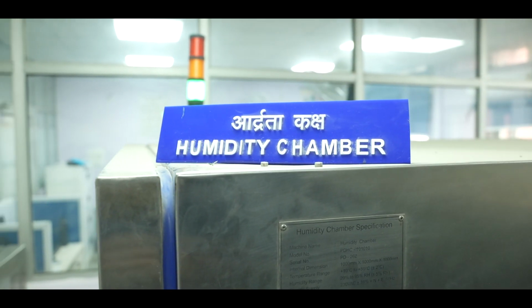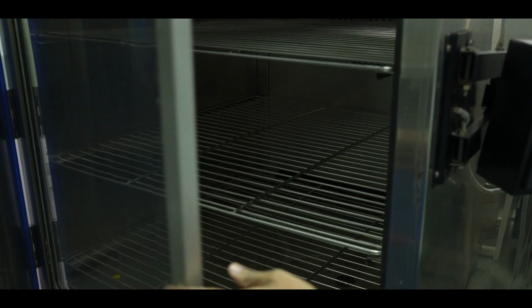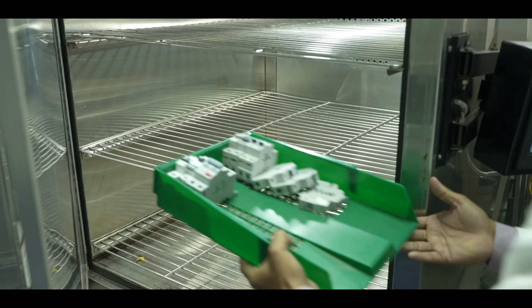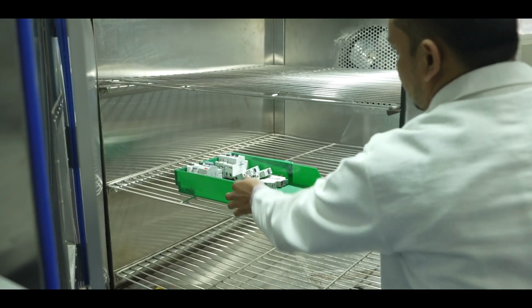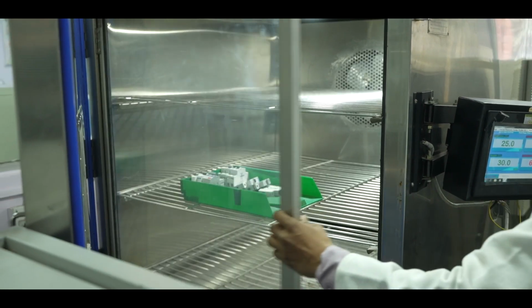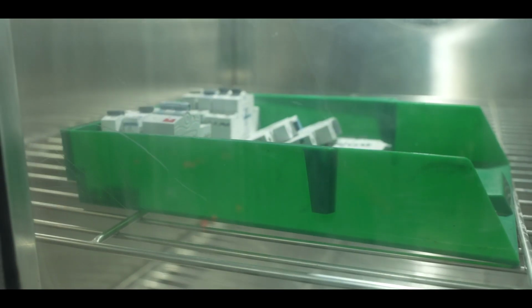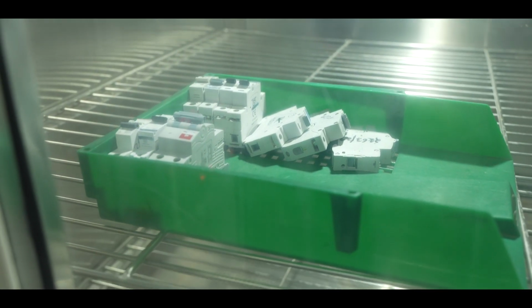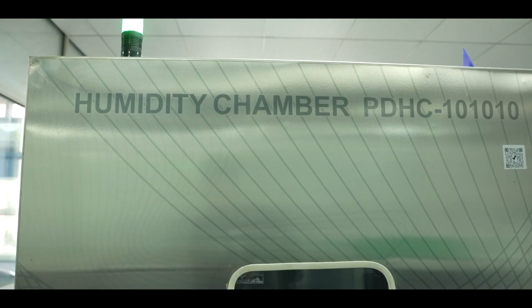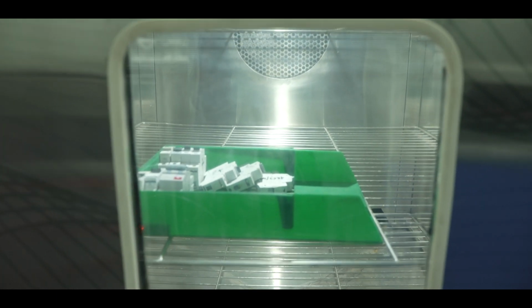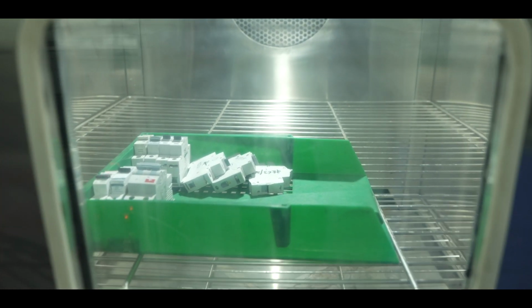Resistance to humidity. In this test, the MCB is exposed to high humidity levels to assess its performance and insulation properties under adverse environmental conditions. The humidity treatment is carried out in a humidity cabinet containing air with a relative humidity maintained between 91% and 95%. And the temperature of the air in which the sample is placed is maintained at any convenient value between 20 degrees Celsius and 30 degrees Celsius for 48 hours.